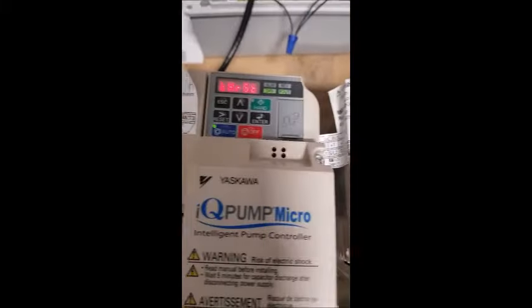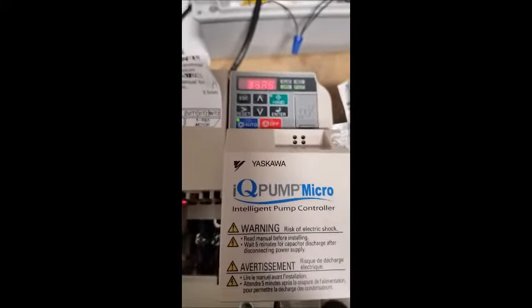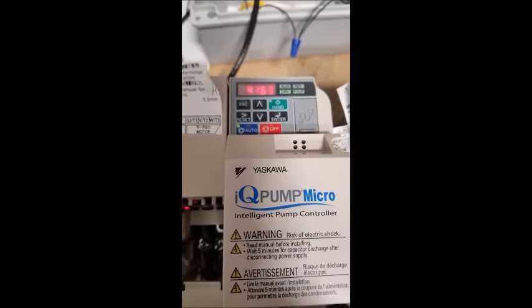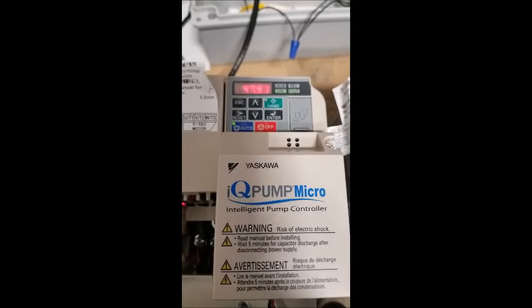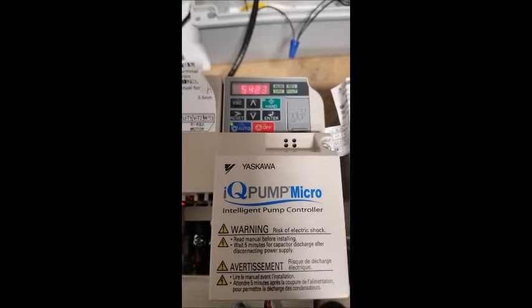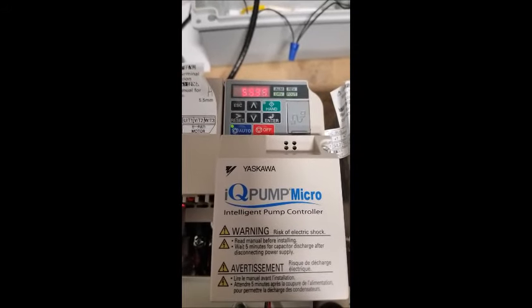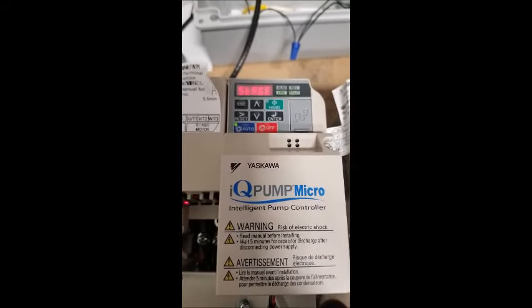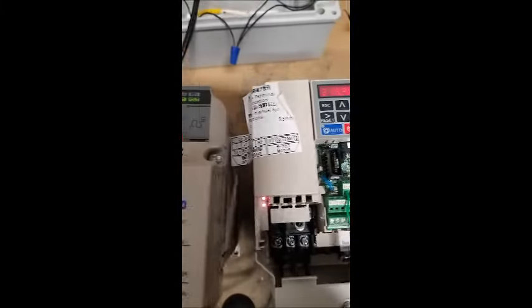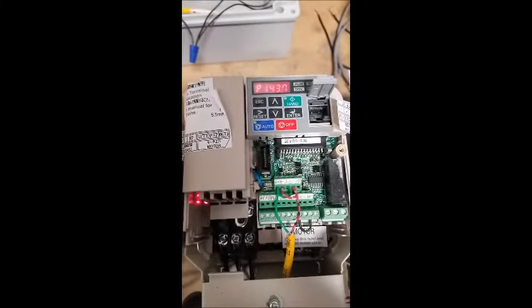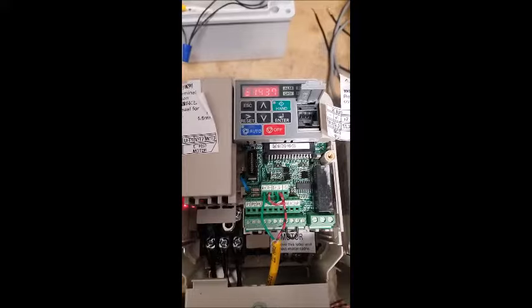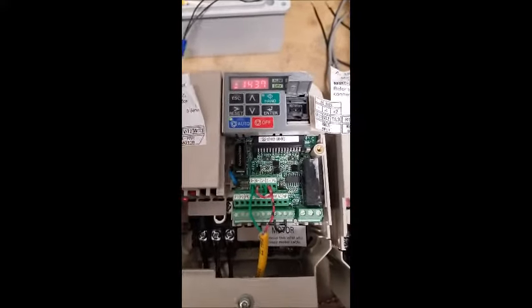Now, if we watch this pressure, as I turn down the potentiometer and the pressure starts falling, the lead drive will wake up and start ramping up. And as the pressure stays the same, it'll keep ramping higher and higher because it's trying to meet the set point. Now once it gets to 60, it's going to say stage, and it's going to wait 10 seconds, which is the stage delay time that we have, and the second drive will be staged in.